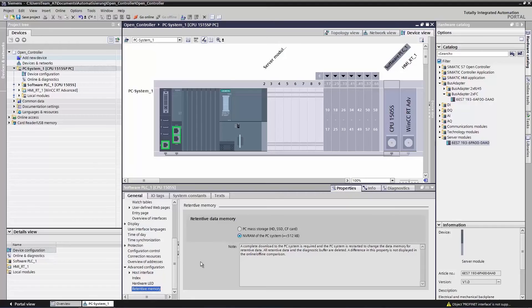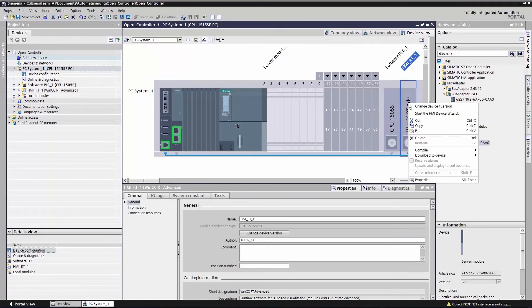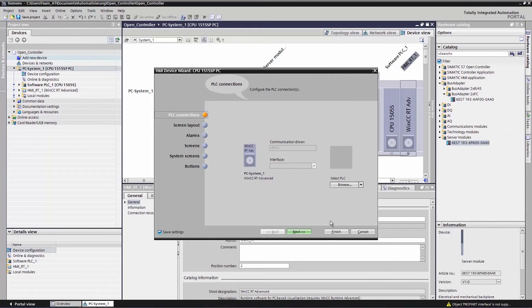For our project at hand, we will need an HMI as well. We will use the HMI wizard to create some system images with a relevant navigation. Right-click WinCC Runtime Advanced in the device view and select the HMI wizard. Simply apply all default settings and close the dialog. The HMI wizard will now generate the required images in the background. We will now need an HMI connection between WinCC Runtime and the software controller for those two components to work together correctly.